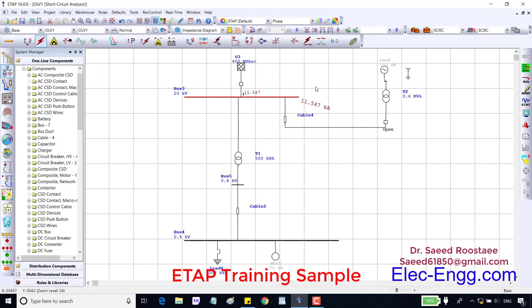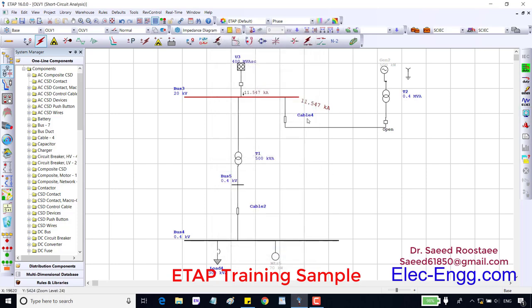As we can see, 11.547 kiloamp is the short circuit current in this busbar. This value is equal to the short circuit rate of the power grid. If we change the power grid short circuit rate, then this current also will be changed.